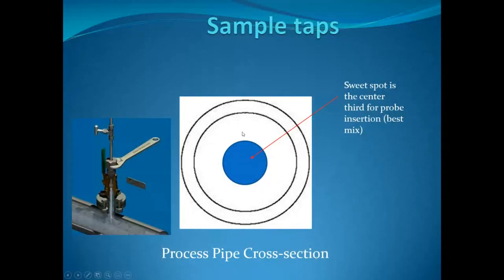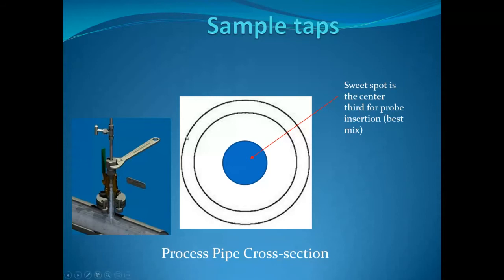It's important to consider where you pull your sample from. Some processes are well mixed, some are not; some are liquid, some are gas. Where we pull our sample from varies by application. Ideally you want a proper representation of what's going on inside the process. As a general rule, you pick from the center third of the pipe, because everything is hopefully mixed well enough there to give the most representative sample of the cross section.